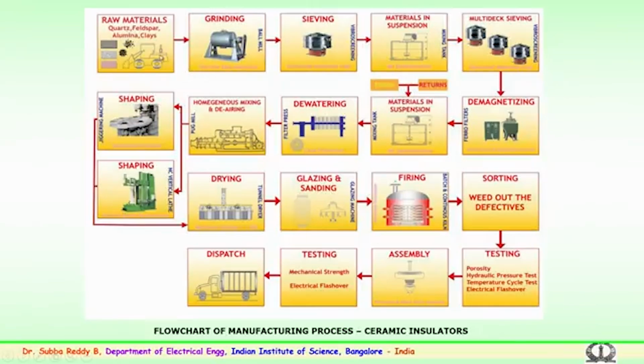Initially the raw materials, which consist of clay, feldspar, alumina etc., are procured and ground using ball milling. Further, this ground material is passed on for sieving, where the material is kept in a suspension in which the water, comprising one part to 3 parts of the clay material, has to be removed. After the multi-stage sieving and water removal, it is sent for the shaping of the insulator.